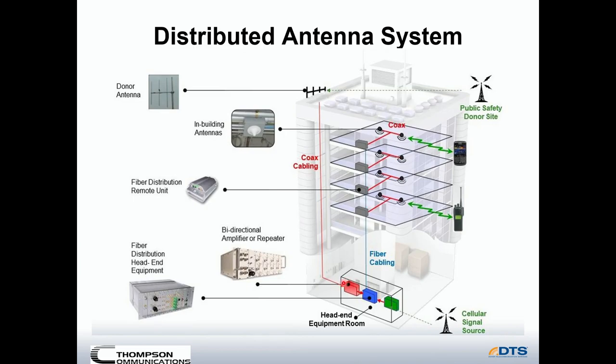Once the signal comes out of the repeater, it's changed into just data and goes into a fiber distribution unit. Once the signal is changed to data, it travels through the fiber network to fiber distribution units on the various floors, where it's converted back to an RF signal and then sent to an antenna or antennas on the various floors.